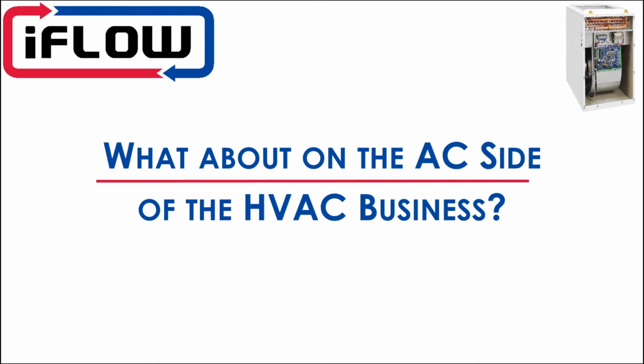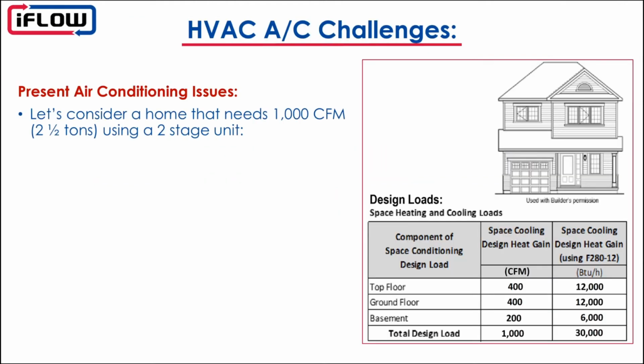Now let's look at the AC side a bit. Let's look at a home, and I've just gone through some basic numbers here. These are all fictitious, but just to give you an idea. On the cooling side, we have 12,000 BTUs for the top floor, 12,000 BTUs for the ground floor, 6,000 for the basement, for a total cooling load of 30,000 BTUs, so 2.5 tons. Given that 2.5 tons, we're going to approximate 400 CFM for the top floor, 400 for the ground floor, 200 CFM for the basement.